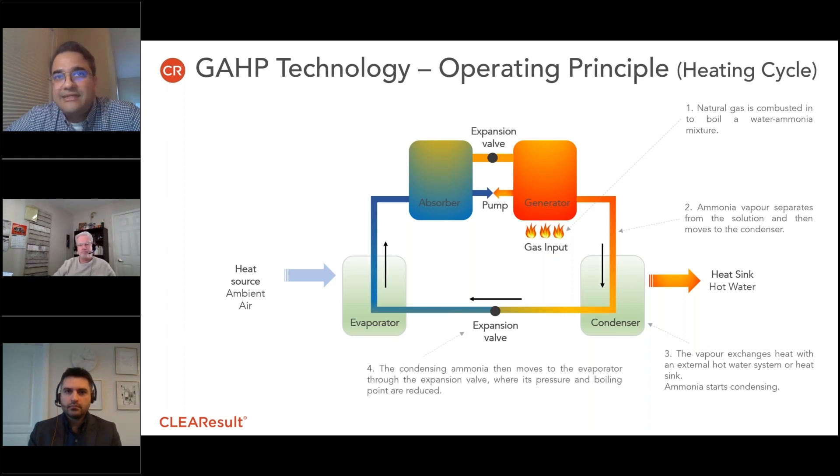This heat exchange cools the ammonia and it makes its way to the expansion valve starting to condense. The expansion valve reduces the pressure and the boiling point of the ammonia, which then enters the evaporator where we have free heat collected from the outdoor or ambient air.